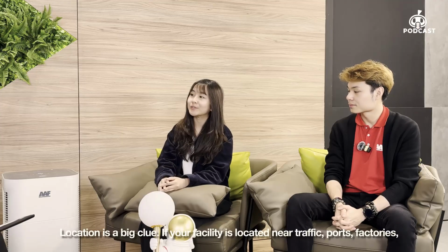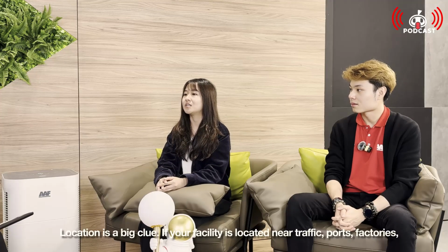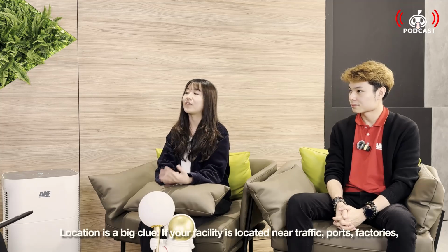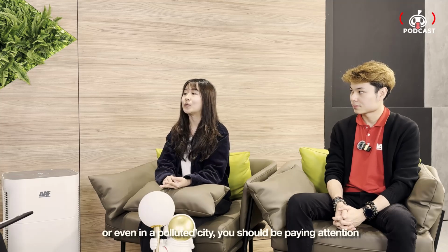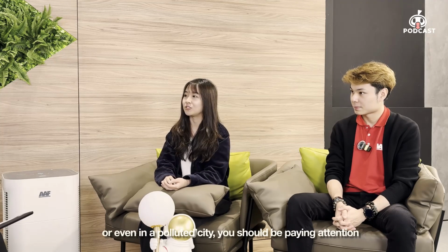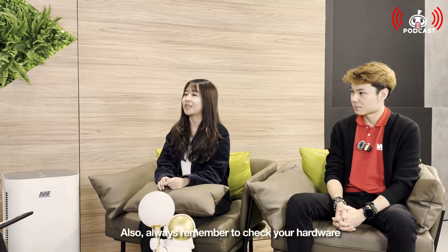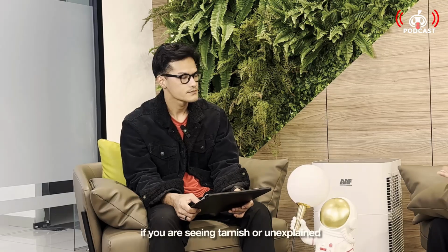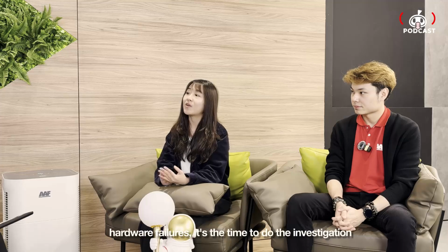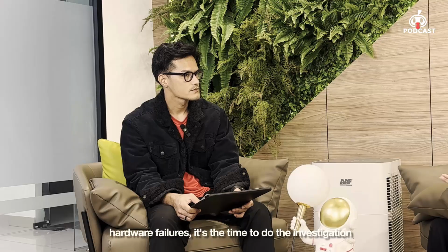Alright, for those listening, how do you know if you need gas phase filtration? Location is a big clue. If your facility is located near traffic, ports, factories, or even in a polluted city, you should be paying attention. Also, always remember to check your hardware. If you are seeing tarnish or unexplained hardware failures, it's time to investigate.